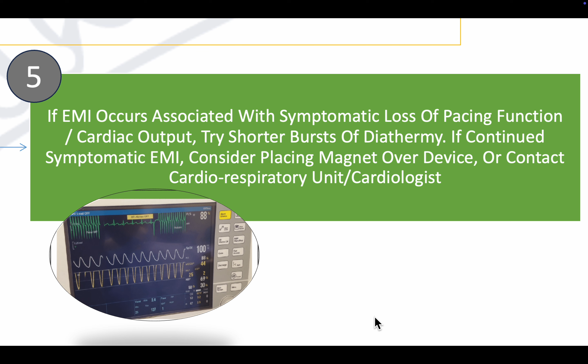Now, if electromagnetic interference occurs with the use of diathermy and it is associated with symptomatic loss of pacing function or cardiac output, then ask the surgeons to use short bursts of diathermy. If this continues, that is, the patient remains symptomatic, then consider placing a magnet over the device, or get the cardiorespiratory team to come and disable the function or change it to asynchronous mode.